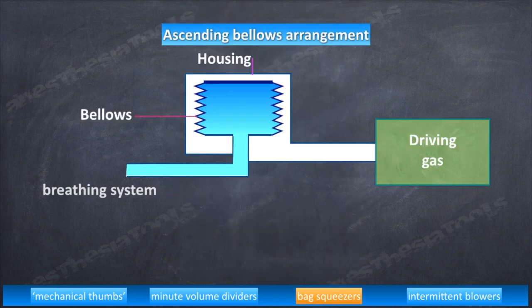The one we discuss now is ascending bellows type. In the event of a circuit disconnect or significant leak, an ascending bellows would not fill or would improperly fill during exhalation. This provides clinicians a visible monitor of ventilator function. Because of the improved patient safety, this type of bellows is generally preferred but does not represent a standard according to the latest document by ASTM.